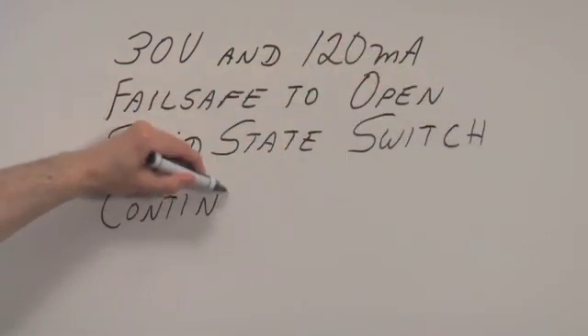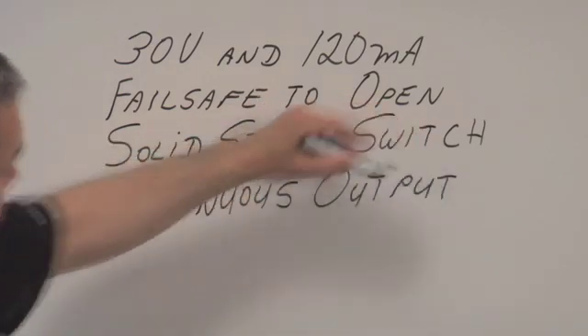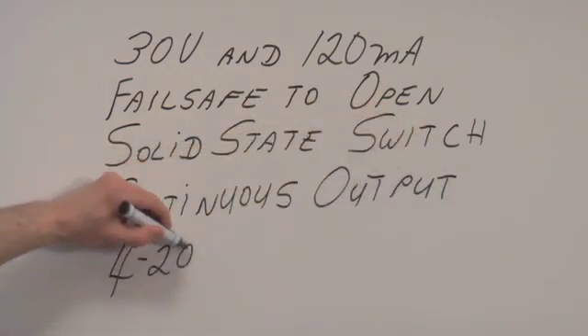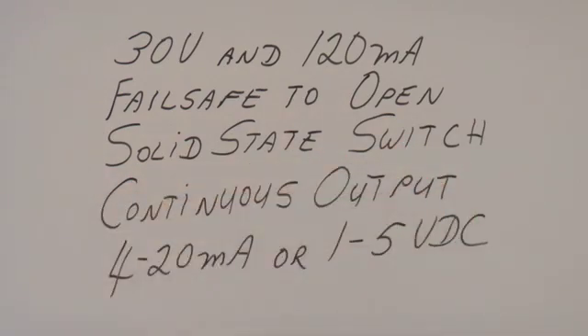In addition to the solid state switch output, the 805QS also provides a supplemental continuous output, either 4-20mA or 1-5V DC. Lastly, the discrete and continuous outputs of the 805QS are independent from each other.